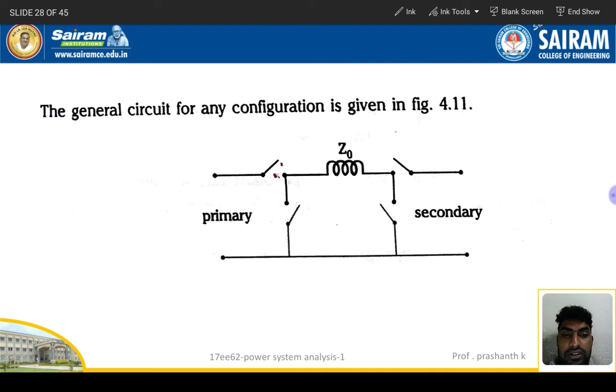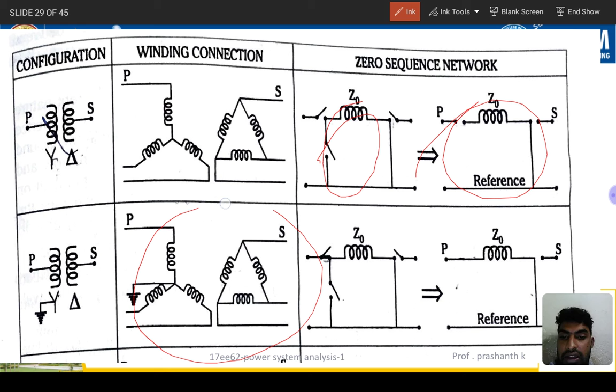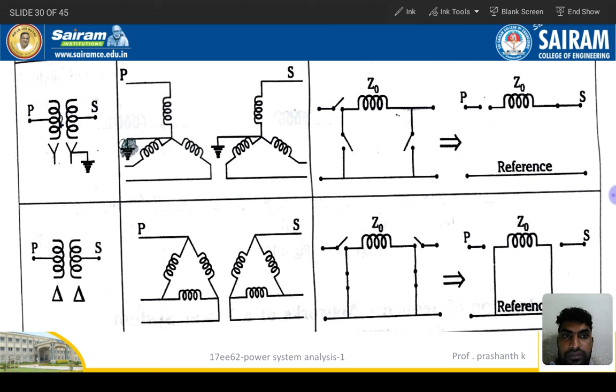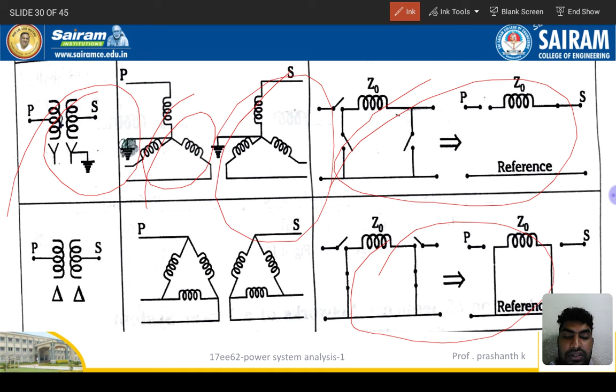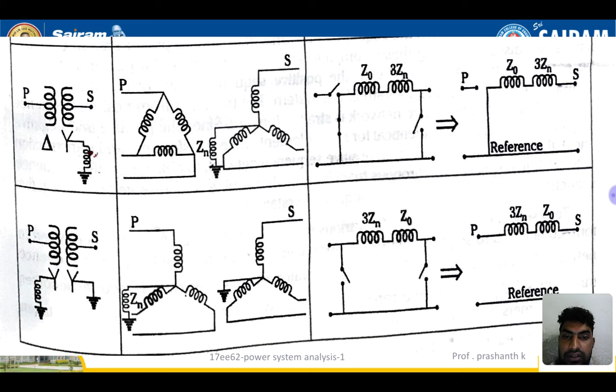This one is a star-delta transformer: this side is star, and this side is delta connection for zero sequence. This one is star to star, and zero sequence components for that. Next there is star to star grounded - here, star to star grounded, and this is the zero sequence components. This one is delta connection. Just remember these diagrams, and then you can design these power system components and solve more problems. Similarly for delta to star and star to star, similarity will be there. Just go through that similarity to understand the concept.